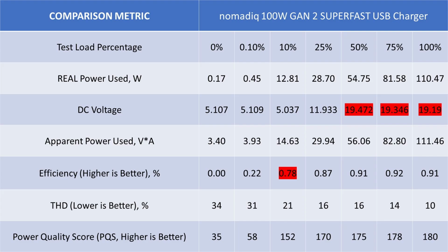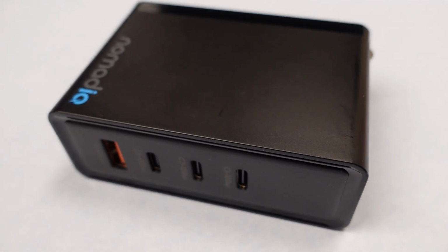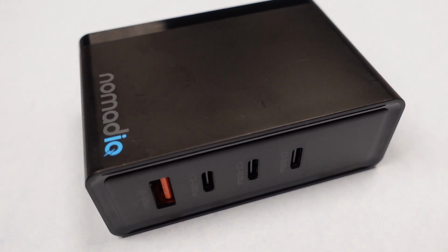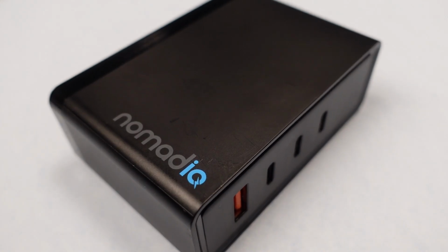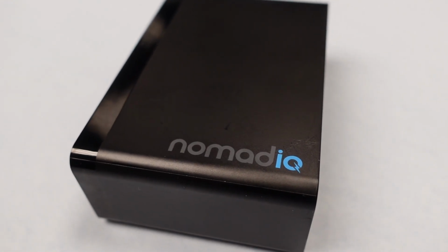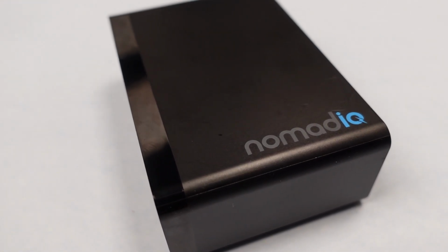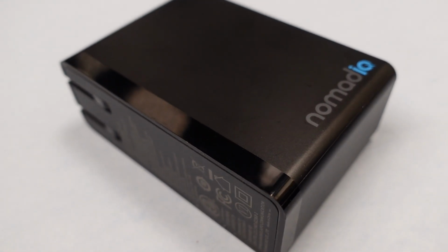The data on this one is mostly good. It is efficient, but not the most efficient. It has power factor correction, but it is not the best implementation I've seen. The voltage is low on the DC side, and that can matter for your charging needs, so I don't like this. This pretty much sets this as a not winning device.